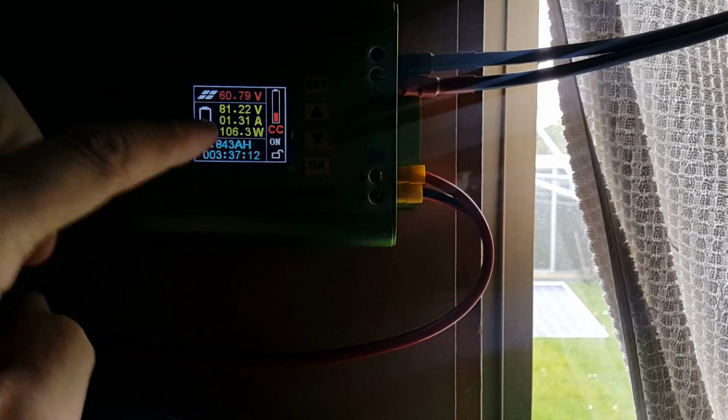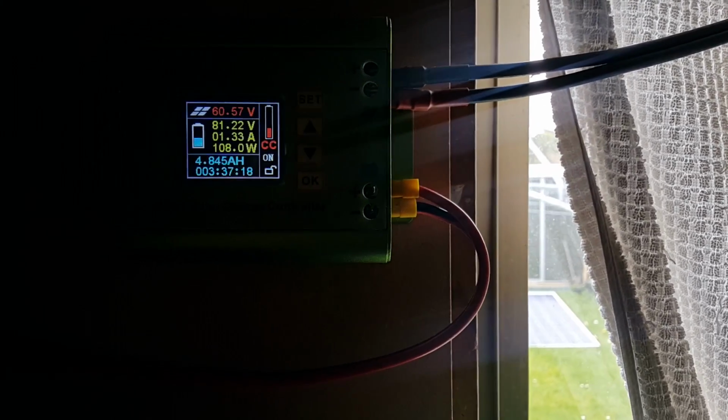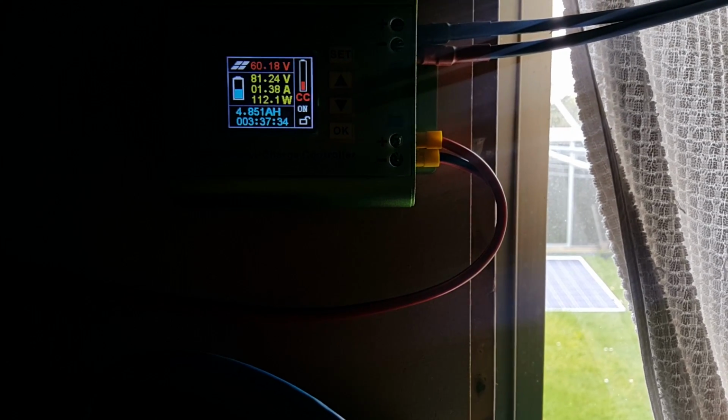And once it's cleaned itself back up again, as you can see, the power starts going back up again. So that's a bit of a fault of this unit. It works perfectly well apart from that one fault, which is under shady and light changing conditions. It really craps out and then freezes, waits, and then comes back to life again. So the tracking of the MPPT is really bad. It's shocking, to be honest, and it's just really slow. Where a normal MPPT will change with those conditions quite quickly and adjust its parameters, this unit shits itself.